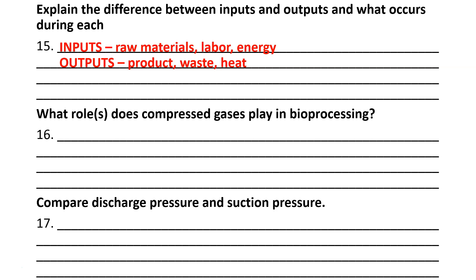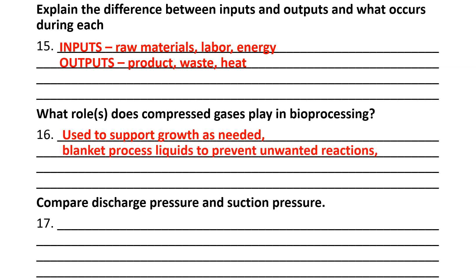What roles do compressed gases play in bioprocessing? There are roughly four. They are used to support growth as needed. They blanket process liquids to prevent unwanted reactions — for instance, oxygen may be needed in some places, but in others it causes unwanted reactions, so we blanket it with an inert gas like nitrogen or argon. They also provide power to operate valves and other equipment. Additionally — and I apologize for leaving this out of the presentation — they are used to transfer fluids.